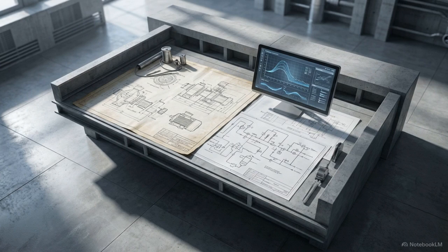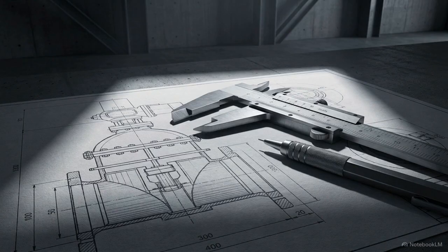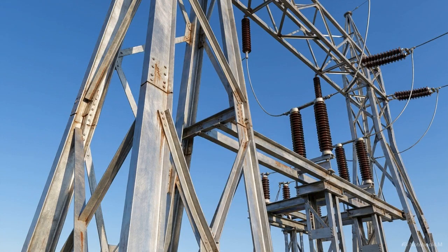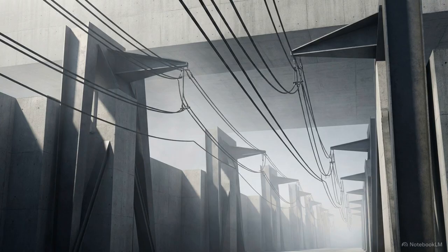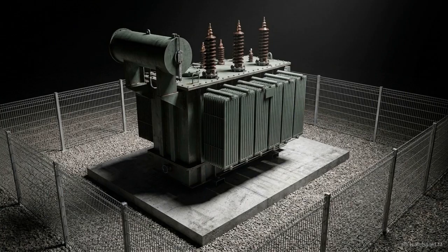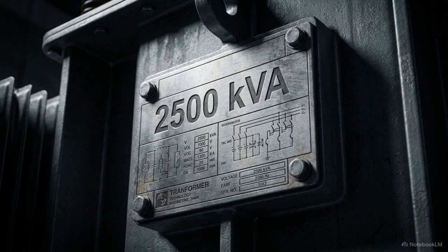The entire electrical, instrumentation, and control architecture exists purely in service of fluid mechanics, engineered to tightly synchronize and carefully dampen extreme physical energies. The process begins at the outdoor structure, where the plant receives its primary power via a 33-kilovolt double-circuit overhead line spanning 18 kilometers from the main utility. That high-voltage current is routed into a pair of 2500 kVA step-down transformers. This specific capacity accommodates the plant's 1102.4 kilowatt running load while reserving a strict 20% margin.